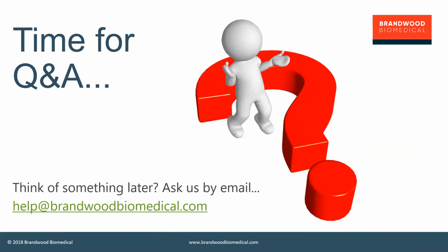So if you're dealing with an implantable, biodegradable device, which is a complex polymer, then you're going to need to do some chemistry, aren't you? You're going to have to look at what comes out, what the degradation products are. That's going to be a substantial investment in understanding the chemistry. Whereas if you're talking about that piece of 316L steel, the only thing you're really going to be worried about there is that you've got a certificate of analysis from the manufacturer that says it is indeed 316L steel, and that you make sure that your process cleans it thoroughly and you know there's nothing left on the surface. You might need to do something to confirm there are no processing aids or sterilant residues left on the surface.